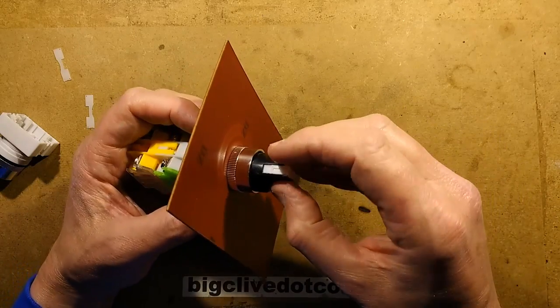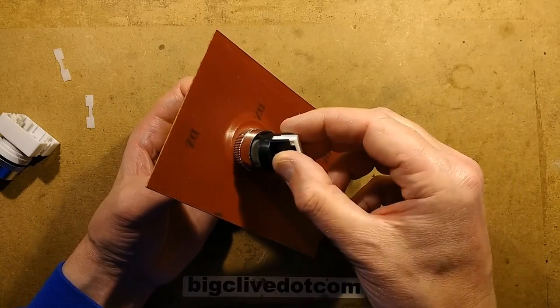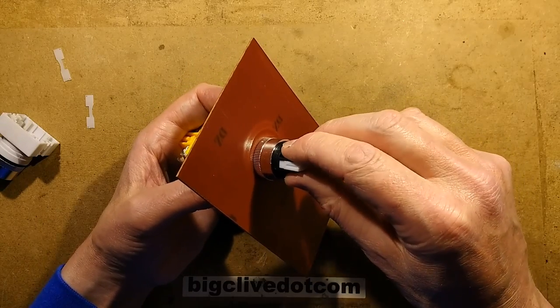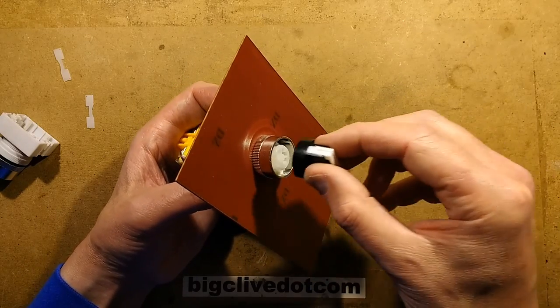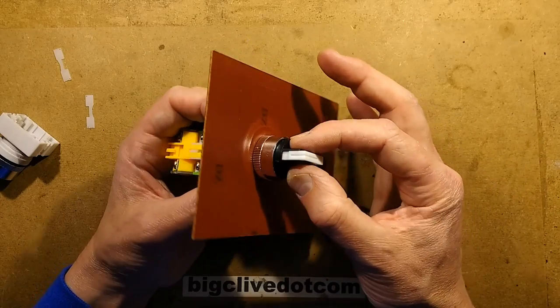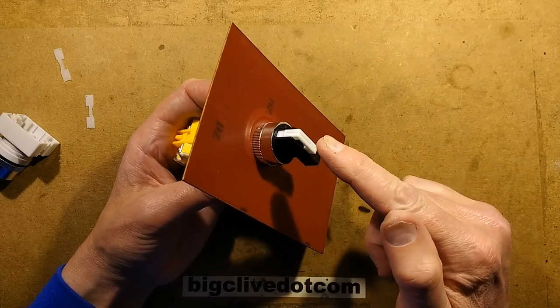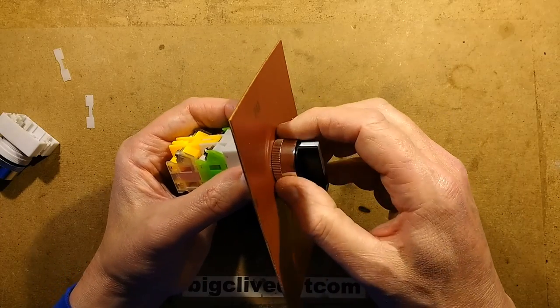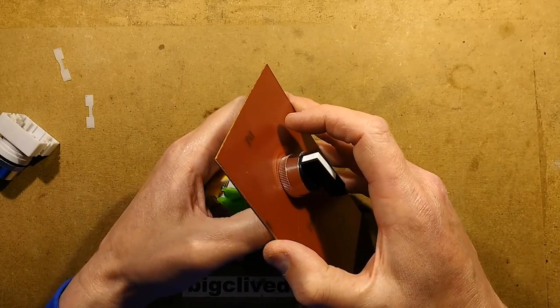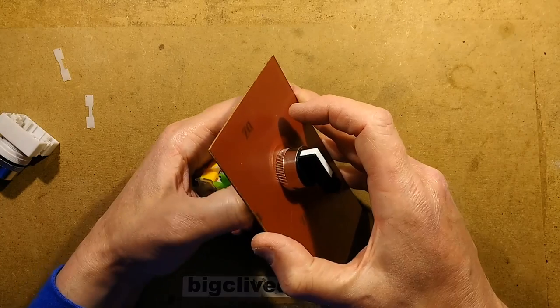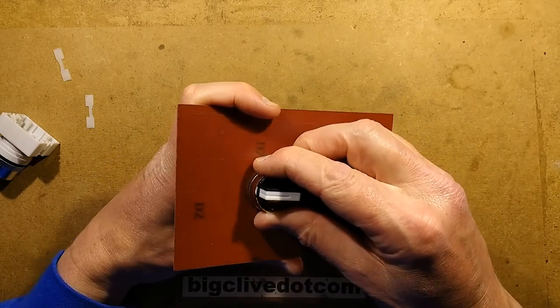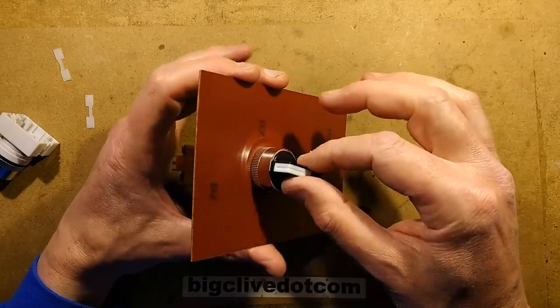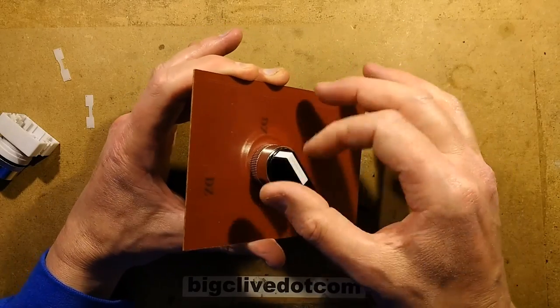So get it in position, and note that when you put this back on it could go on in various positions. So you have to get a feel of where the switch is, get it into its middle position, line the mechanism up pointing in the direction of the off position, and then click this down. At that point I think I'd unwind this out a little bit more, get the lock ring tightened out the back, and then finish it off by tightening the front one just to actually put that under tension so the mechanism can't slip round when you're actually switching into different positions.